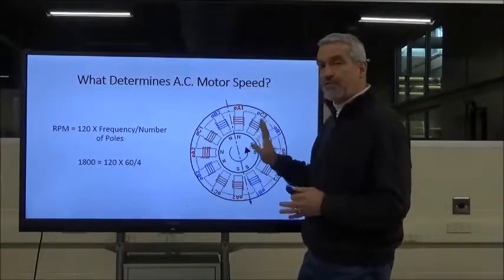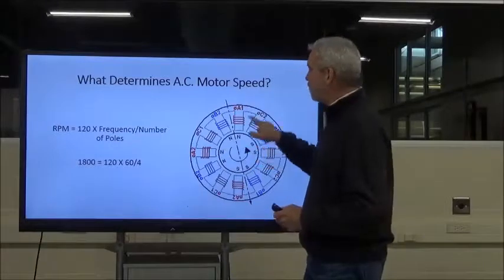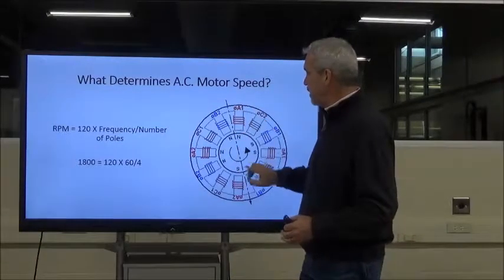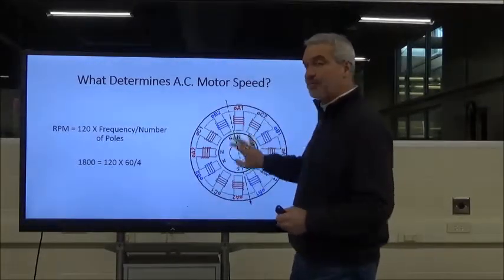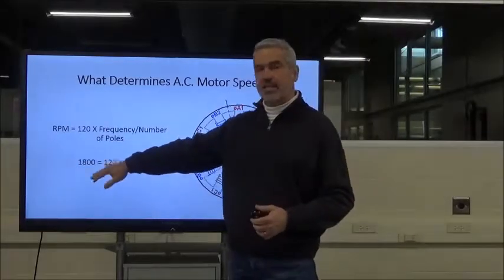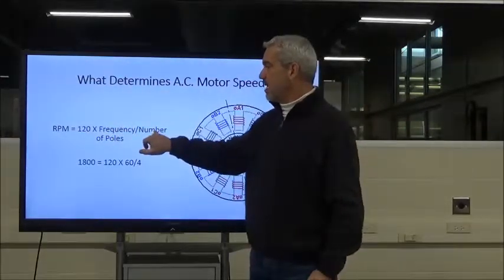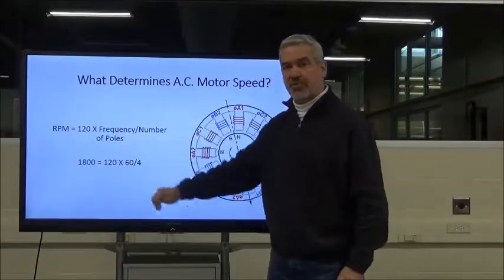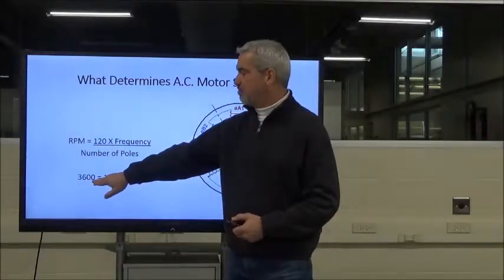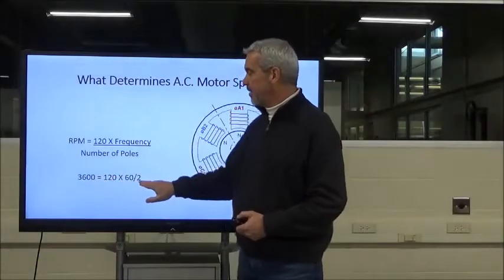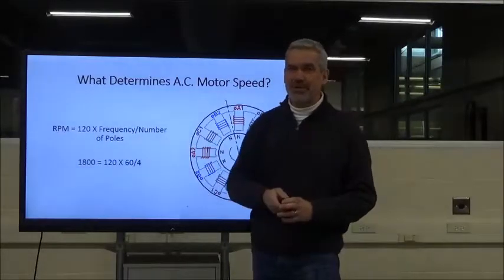With a four-pole motor, using the same formula: 120 × 60 ÷ 4 = 1,800 RPM. Notice that we doubled the number of poles and cut the RPM in half. Going from two poles to four poles drops us from 3,600 to 1,800 RPM. Pay attention to this relationship because you may see it on a quiz.